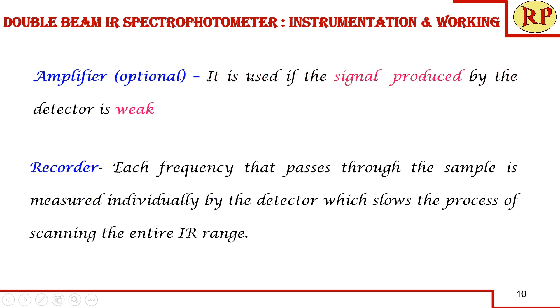An amplifier is optional — if the signal from the detector is strong, an amplifier is not required; if it is weak, an amplifier is needed to enhance the signal. In the recorder, each frequency that passes through the sample is measured individually by the detector, and this process is very slow because it scans the complete IR range.